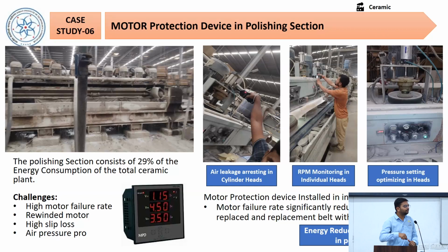Due to their operation error, they are having excess pressure on the cylinders. When we have excess pressure on the cylinders, it converts into excess load on our motor. At that time, the motor is not stopping. After the introduction of this instrument, the motor stops whenever there is excess pressure on the system. So the motor failure rate is eliminated now, and our motor is saved, as when we rewind the motor, 6.6% efficiency is lost.